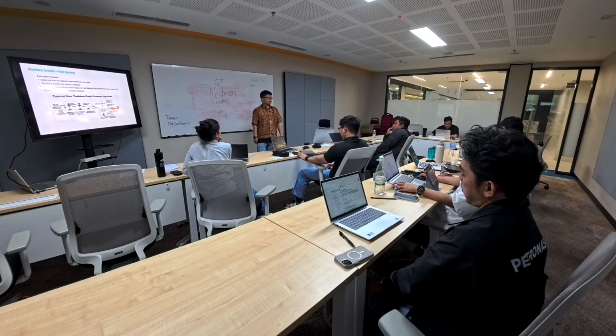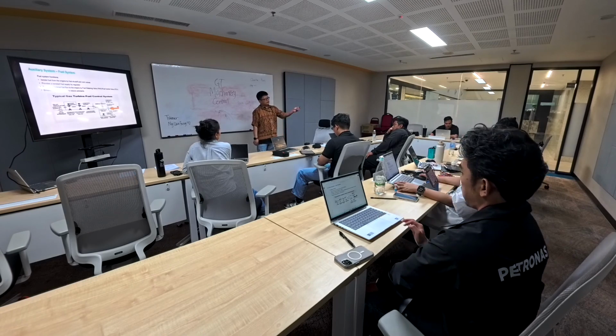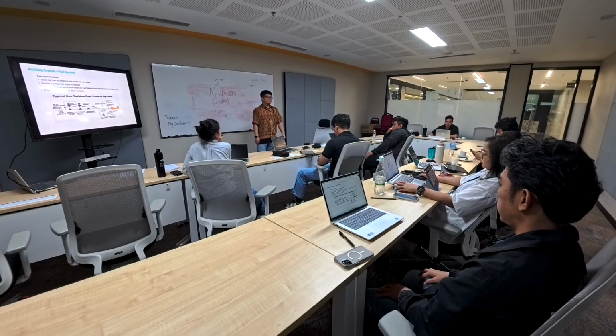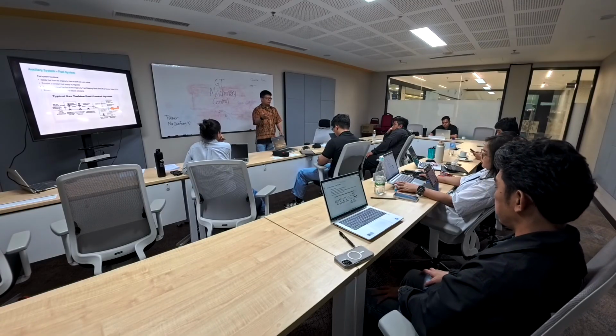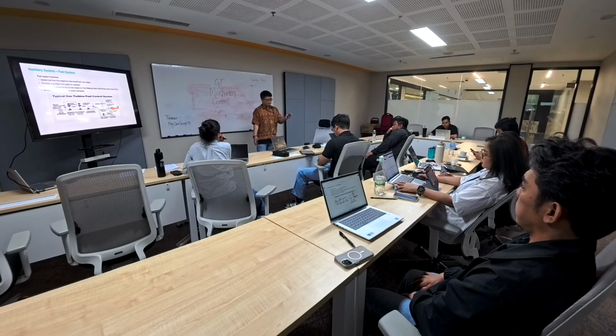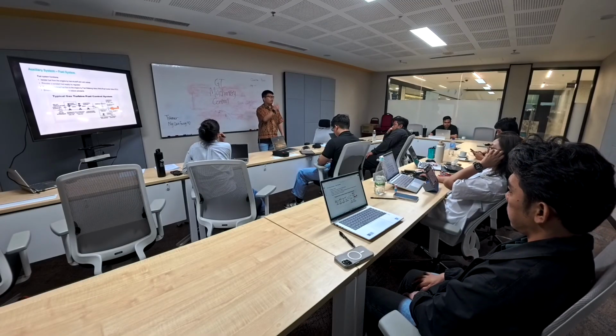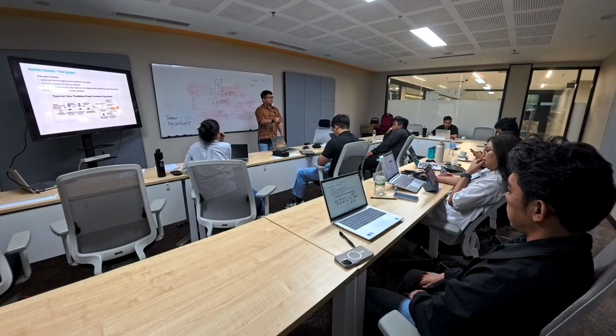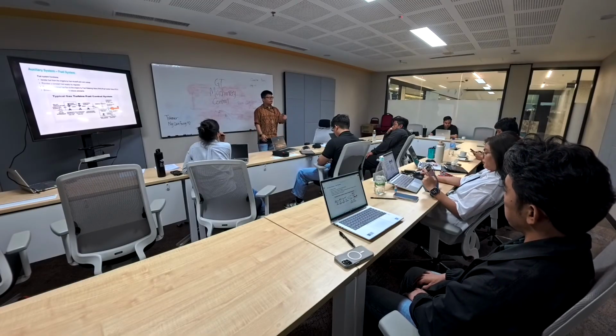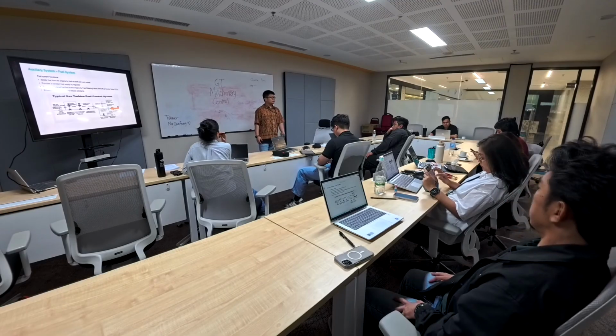That one we can calculate. So how about the parameter change? You will not see so much change in the parameters, for example your T5, you will not see a very big difference. In fact, the fouling itself will give you a bigger influence. So a change in any operating parameter cannot be directly attributed to a change in fuel gas, because fuel gas plays a very small role. Other external factors contribute much more to changes in operating parameters.